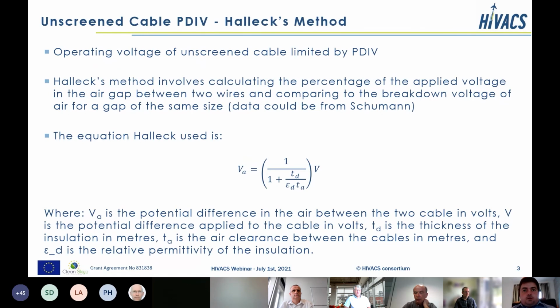So for unscreened, Thomas has already talked about Halleck's method, so I won't go into too much detail. All I'll say is this is the equation for the method, and it takes into account the thickness of the dielectrics and the permittivity of the electrical insulation. And it basically involves estimating the percentage of the voltage in the air gap between two wires, and then comparing the amount of voltage with the breakdown values that have been measured by people such as Schumann and others.